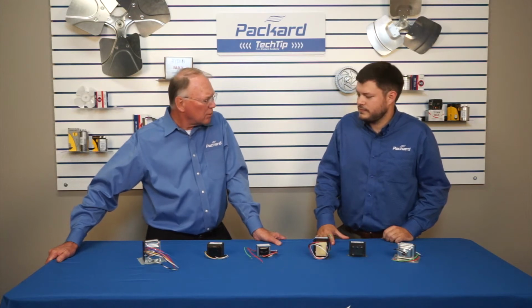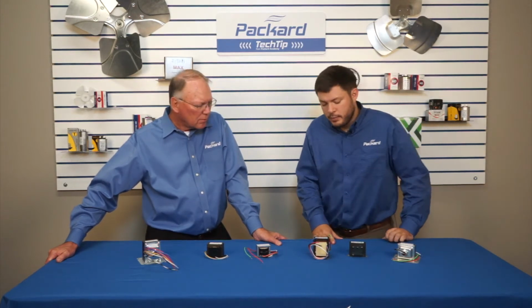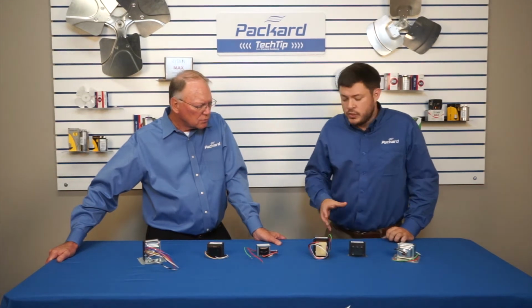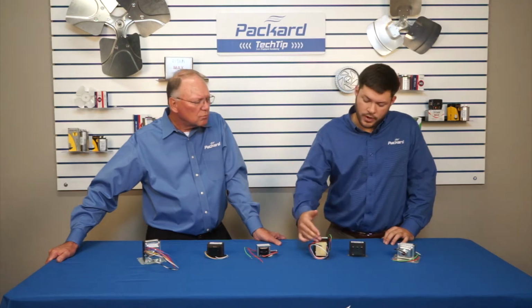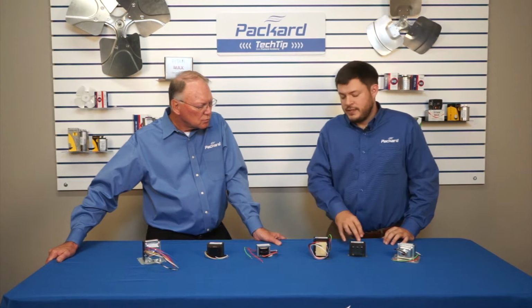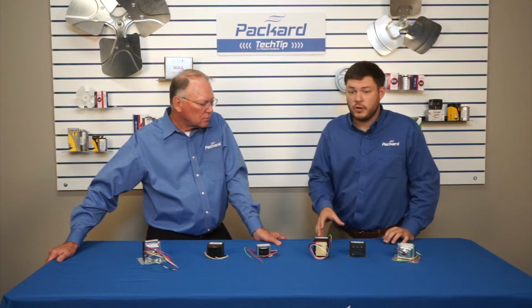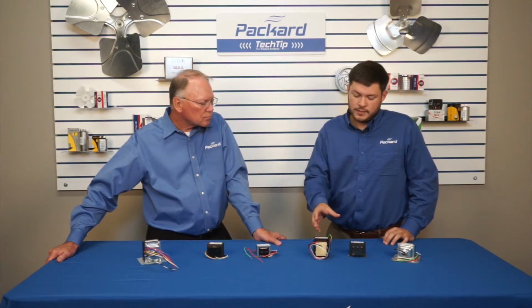What does it do? Transformers are actually fairly simple. A transformer has two separate coils that are independent of each other, so there won't be continuity between a primary side and a secondary side. A specific voltage on your primary side induces a voltage in your secondary side, and that's based on and designed by the number of turns in that coil, as well as the distance from that coil to the secondary coil, and the number of turns in that secondary coil.